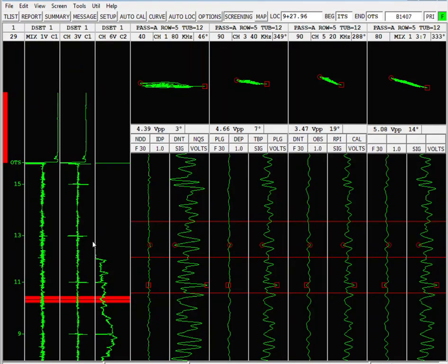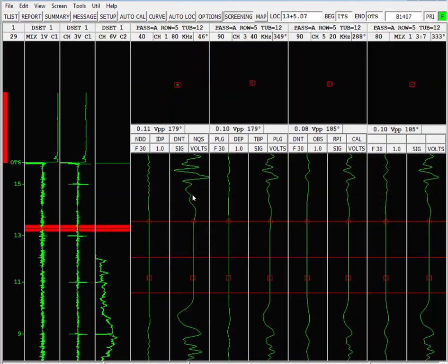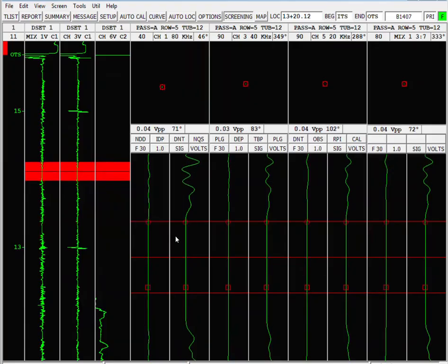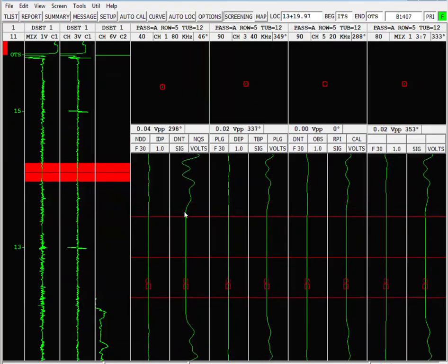So in this data set that you'll download to your computer, there will be a handful of tubes, and each one of those tubes will have at least one dead spot like this. Some may have more than one, but they'll be pretty easy to spot if you just zoom in on your strip charts and look for these dead spots. Again, this data should be rejected and reacquired.